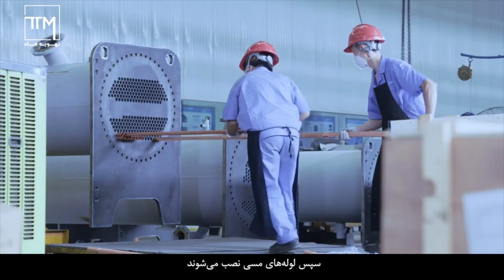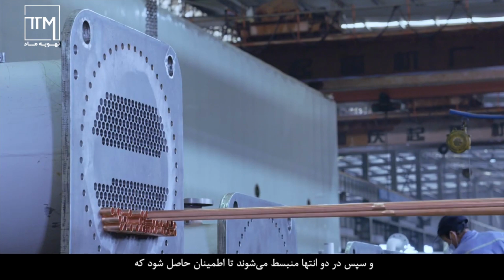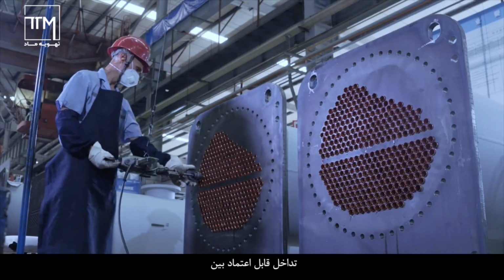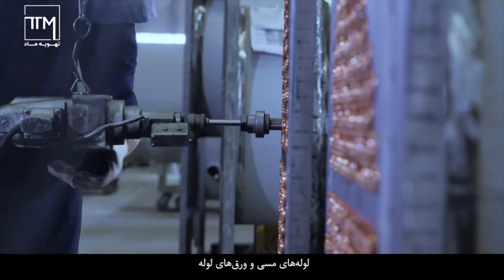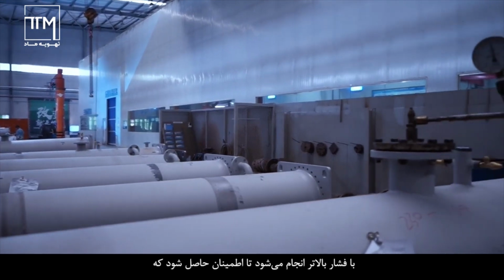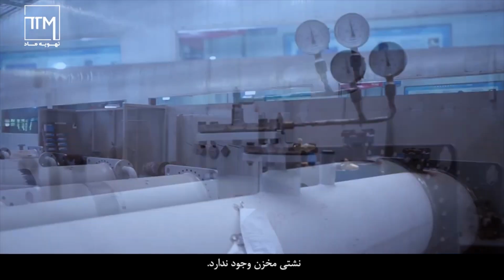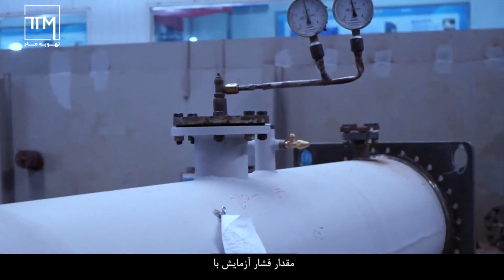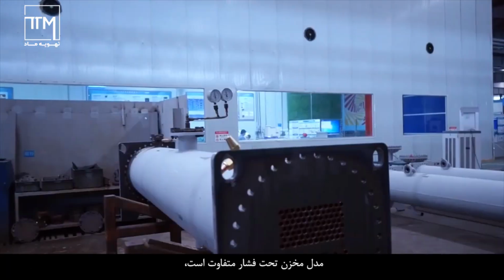Next, the copper tubes will be installed and then expanded at both ends to ensure a reliable interference fit between the copper tubes and the tube sheets. After the vessels are manufactured, the water pressure testing will be conducted at a higher pressure to ensure there's no vessel leakage. The testing pressure value varies with the pressure vessel model.